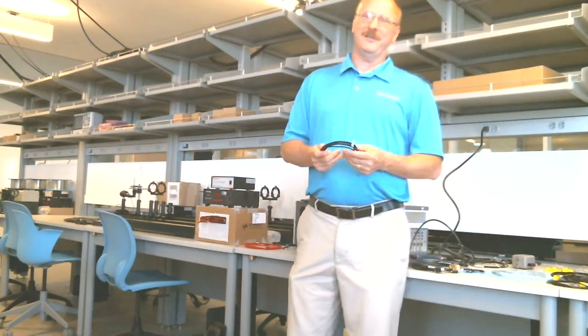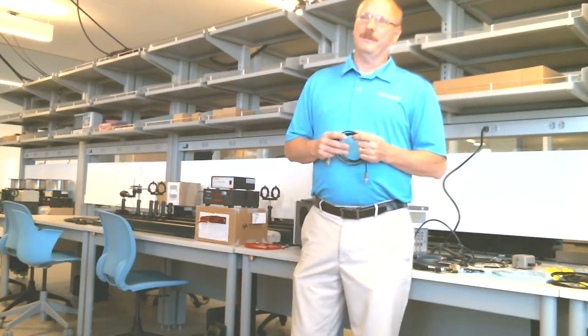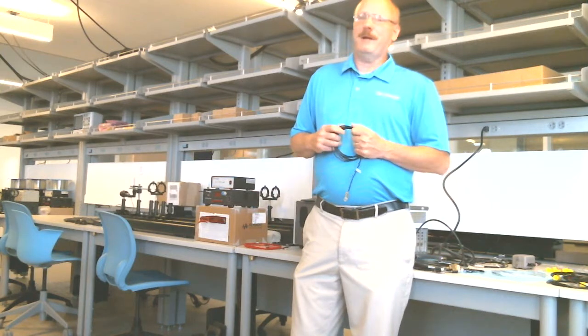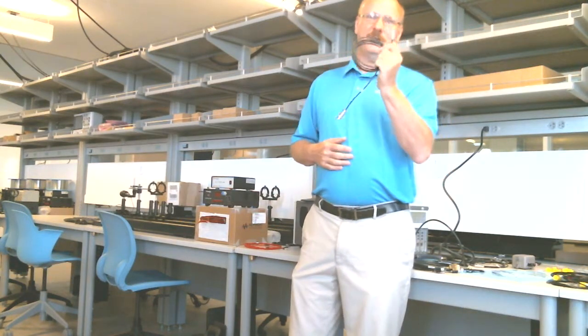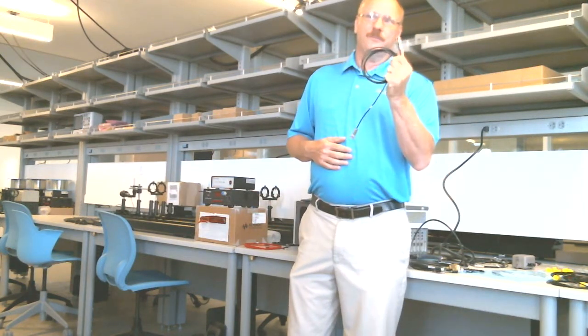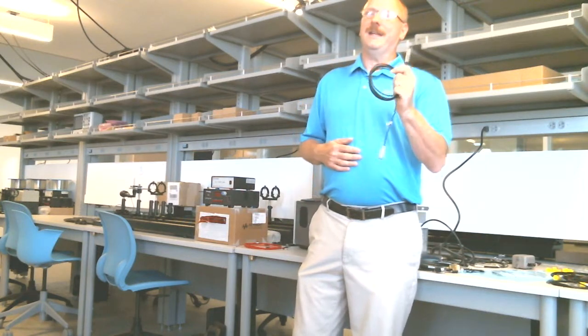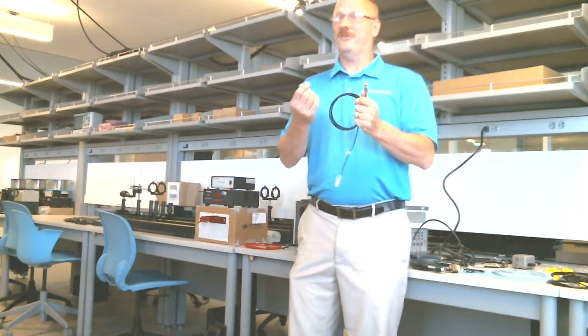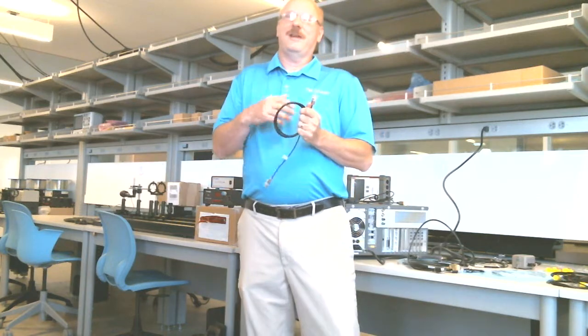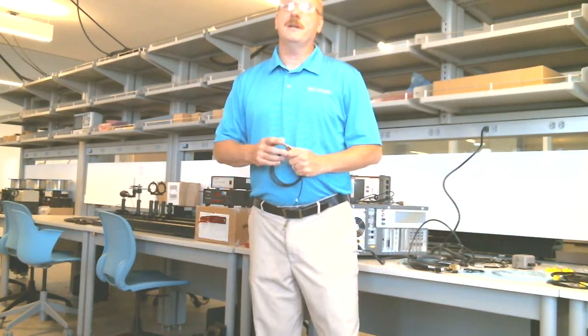I can get rid of that leakage by having that third conductor. If you think about it, if I'm sourcing a voltage through the center of this cable, it's going to leak from that center conductor to the inner shield. There's going to be some leakage that's just part of your measurement. It is what it is.